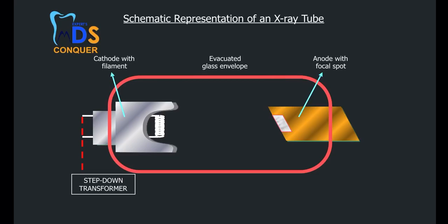It is angulated in order to decrease the size of the focal spot, and that final size is called the effective focal spot size. So in order to decrease the size of the focal spot from the actual size to the effective focal spot size, it is slightly angulated, and the effective focal spot size is 1 x 1 mm. Why is it done? In order to improve heat dissipation and also to increase the sharpness of the image. These are the other reasons for that.